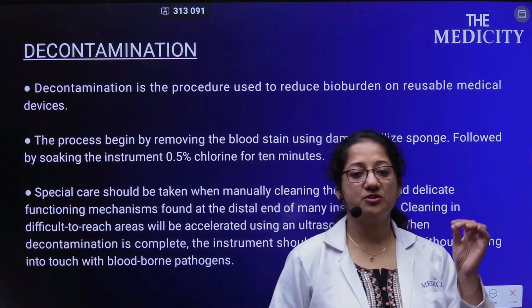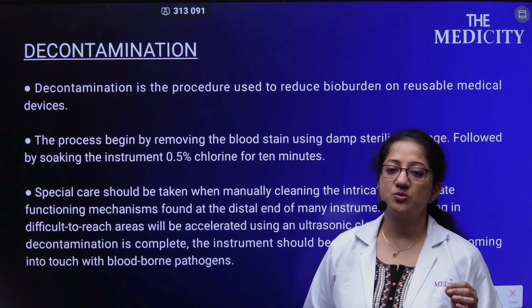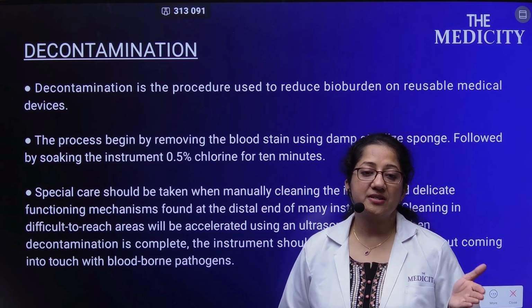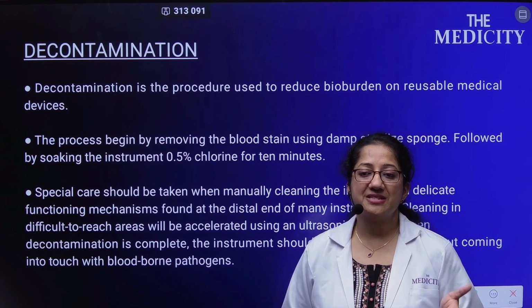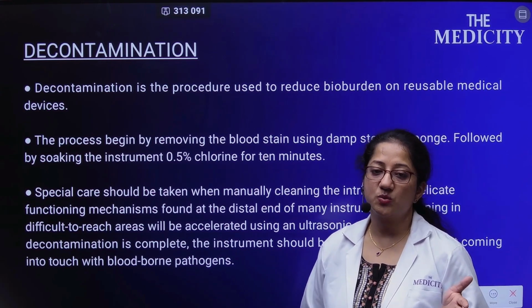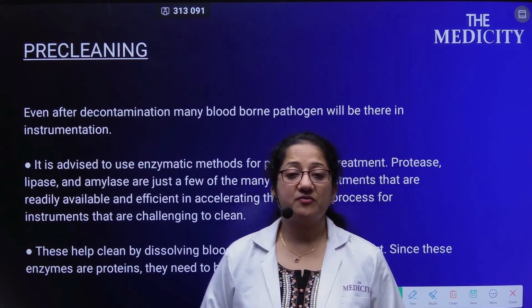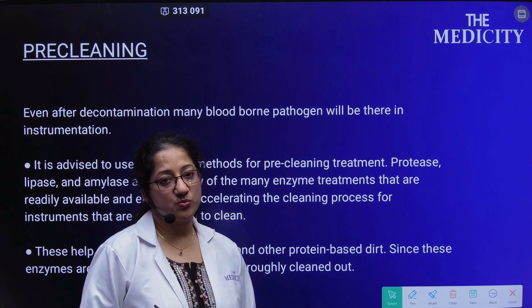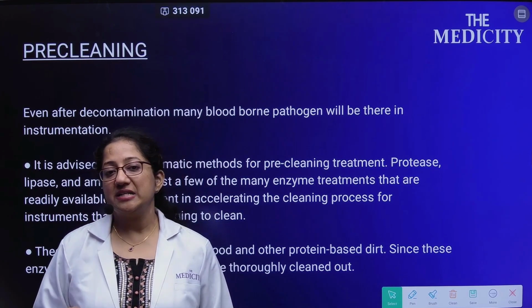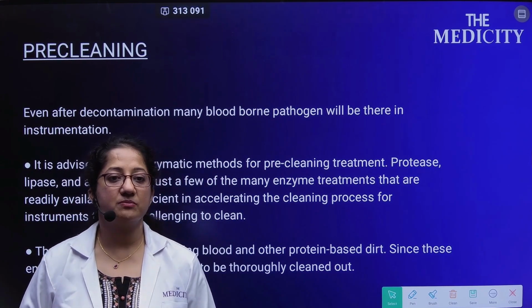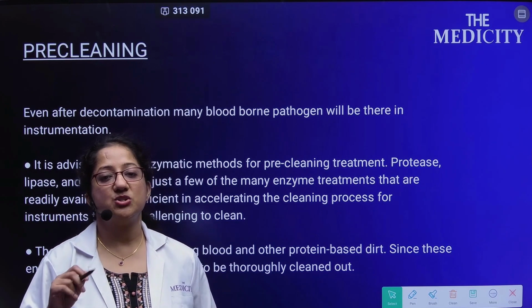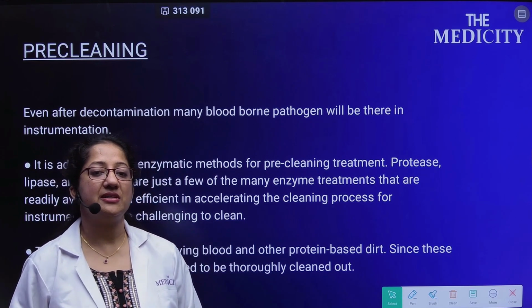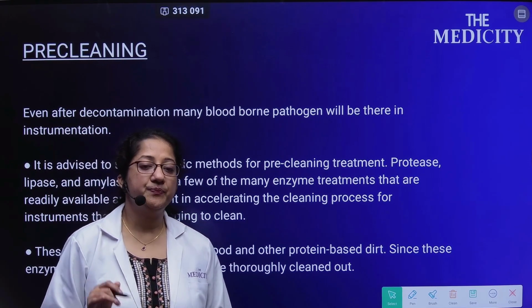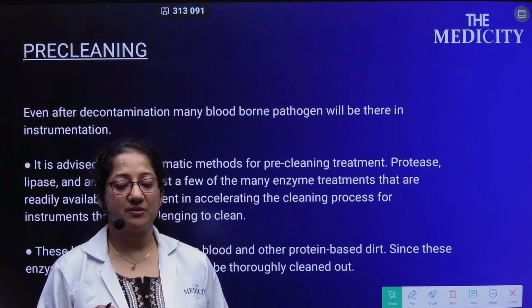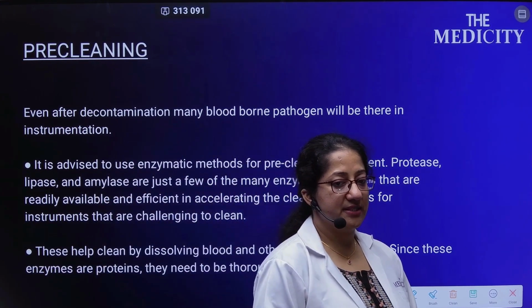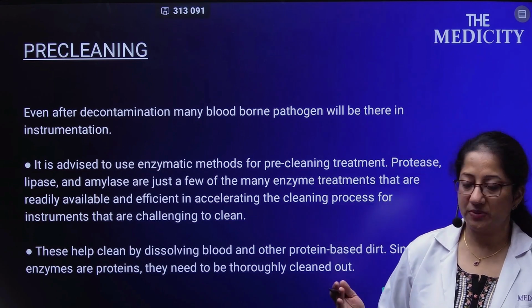Cleaning in difficult to reach areas will be accelerated using an ultrasonic cleaner. When decontamination is complete, the instrument should be safe to handle without coming in touch with bloodborne pathogens. Pre-cleaning: even after decontamination, many bloodborne pathogens will be there on the instruments. It is advised to use enzymatic methods; protease, lipase and amylase are just a few of the many enzymes readily available for cleaning. They help to clean by dissolving the blood and the protein-based dirt. And these enzymes are proteins which need to be thoroughly cleaned out.